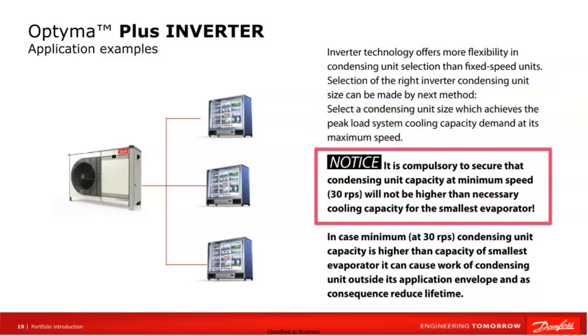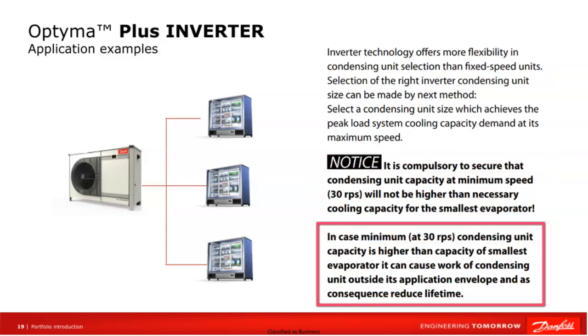Attention! It is necessary to ensure that the minimum capacity of the condensing unit at a minimum speed, 30 revolutions per second, does not exceed the required cooling capacity of the smallest evaporator. If the minimum capacity at 30 revolutions per second is higher than the required capacity of the smallest evaporator, then the condensing unit may operate outside its operation envelope, which may consequently shorten the service life.